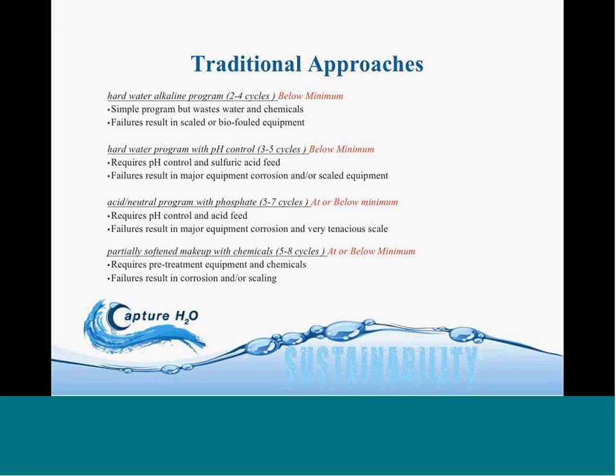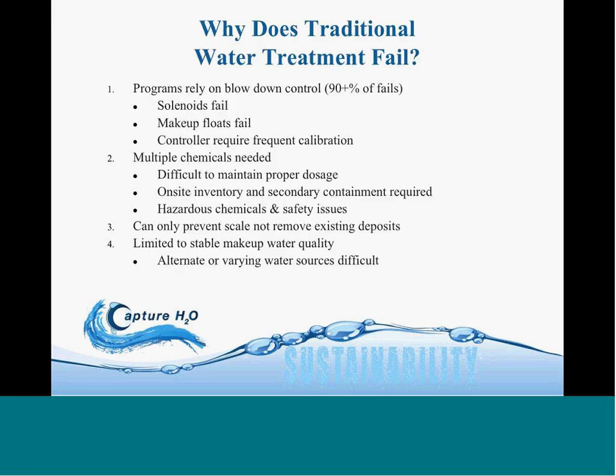You can cycle the water up even higher and get more water conservation, but you increase your risk of failures when you do that because of the pH control and the hazardousness of acid. Finally, you could partially soften the water going to these cooling systems and meet or exceed the minimum of 6 cycles. So that's the traditional water treatment approaches. If you go to the next slide, I'll talk about why these systems have failures.